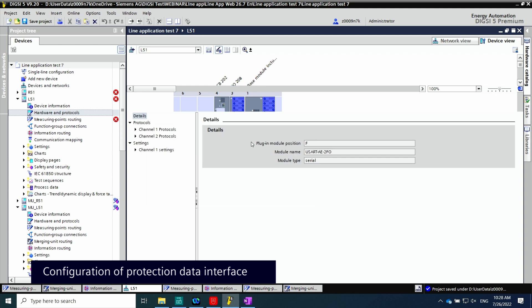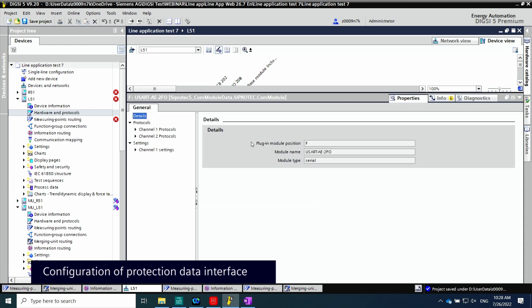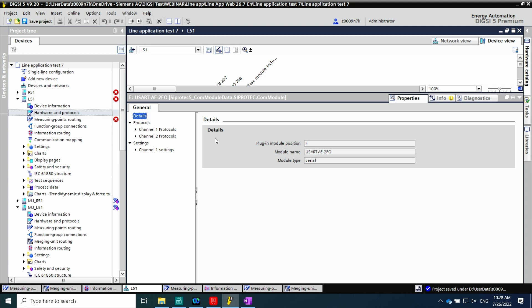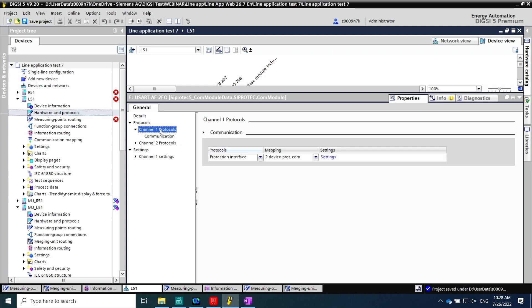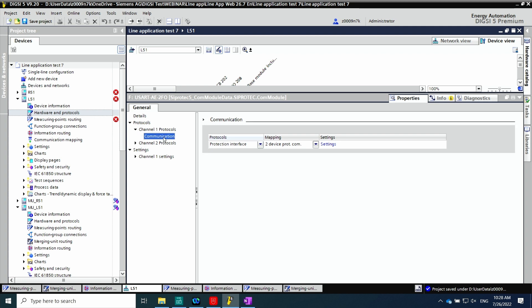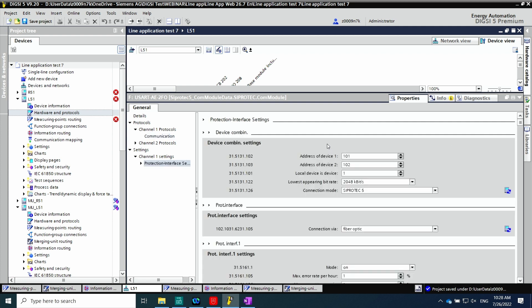For line protection, there is another card to achieve communication between the two substations. The protection data interface is needed, which is available in the protection device. It permits us to communicate two relays located in two different stations. Here we can give the address of each device — for example, local device 101 or remote device 102.